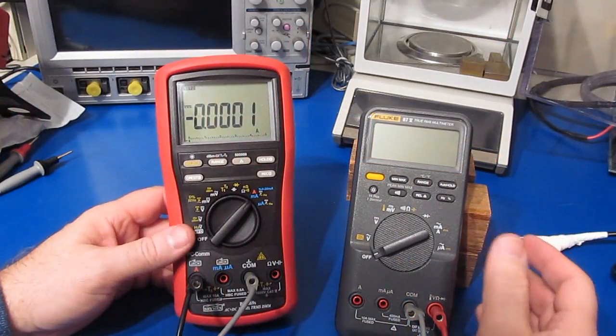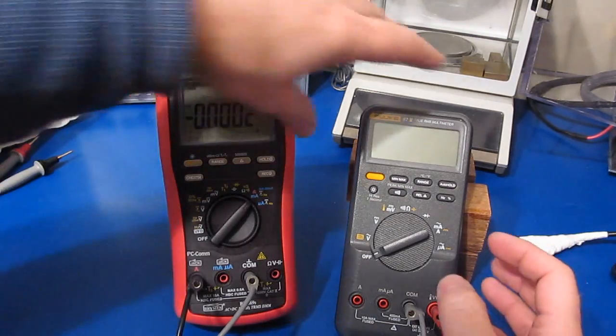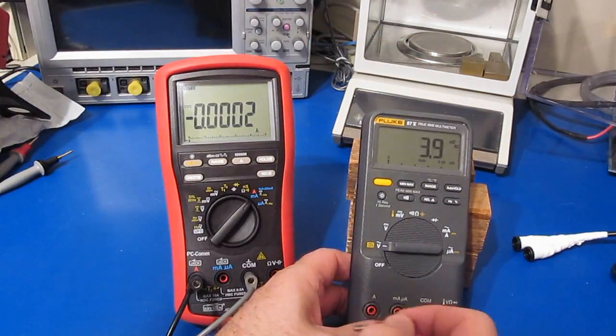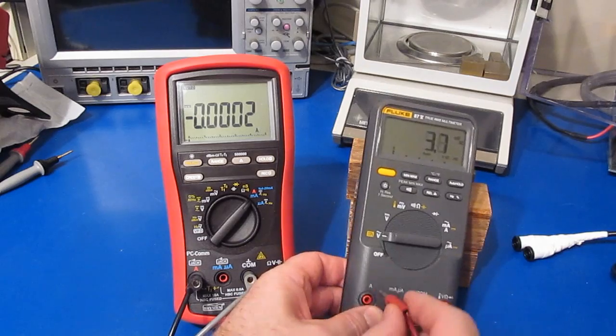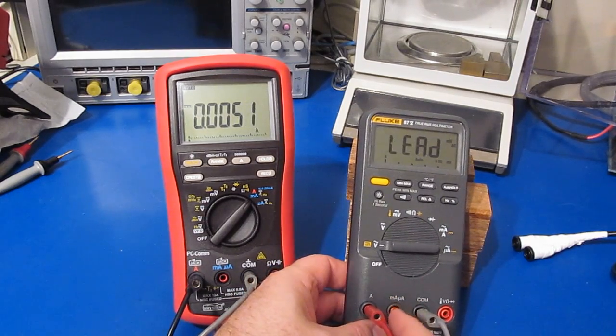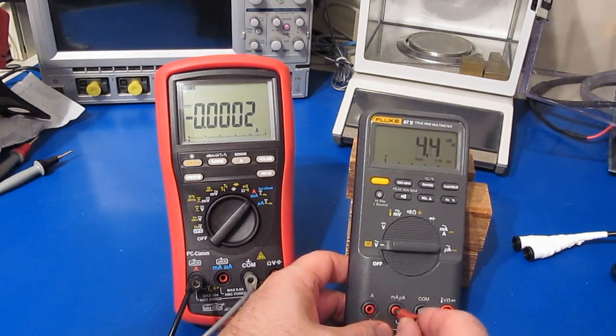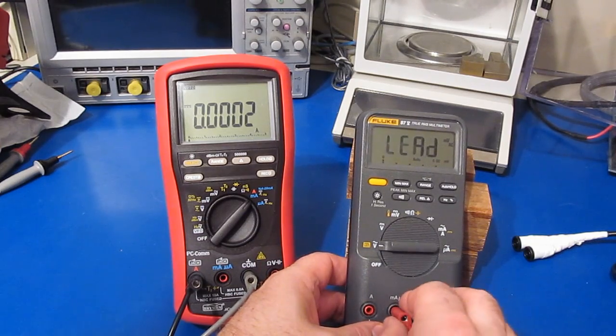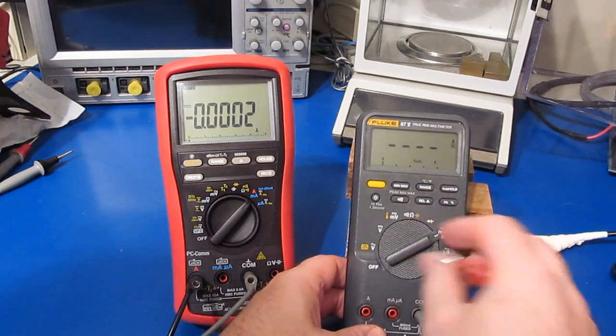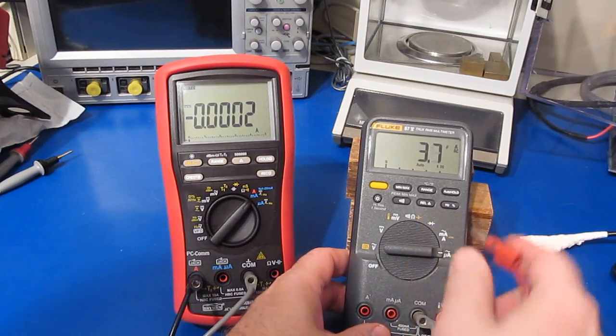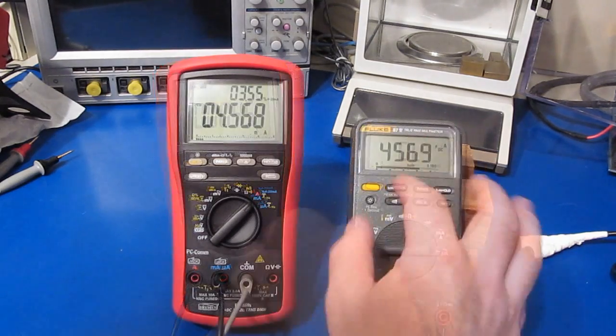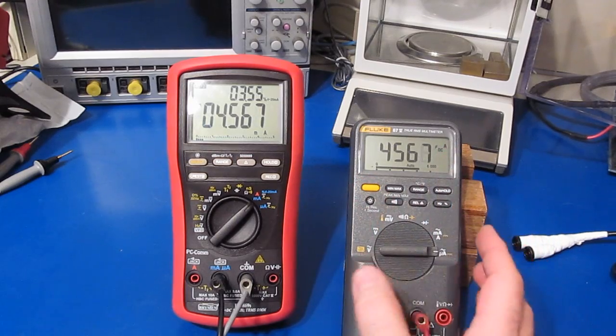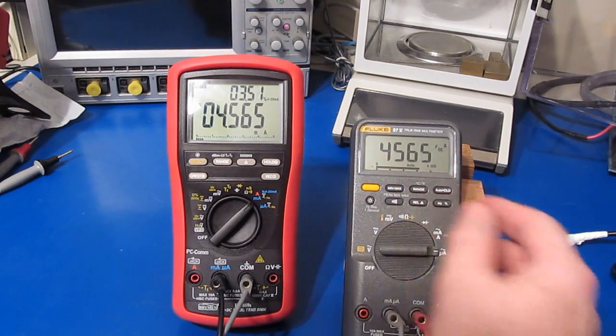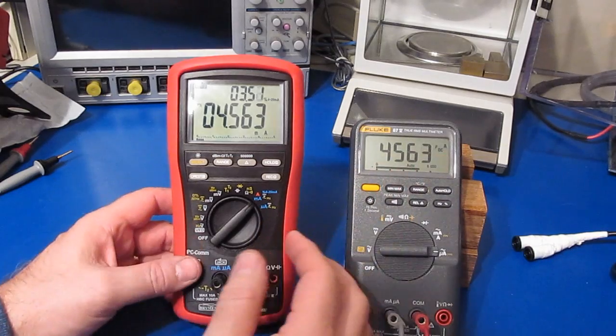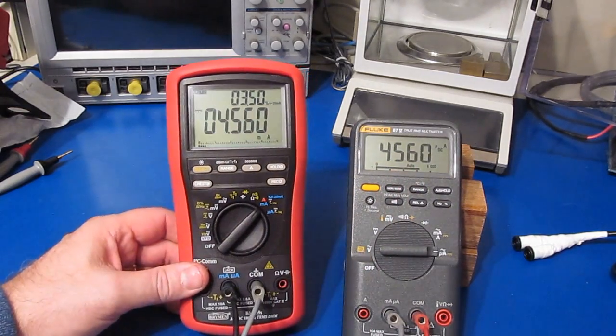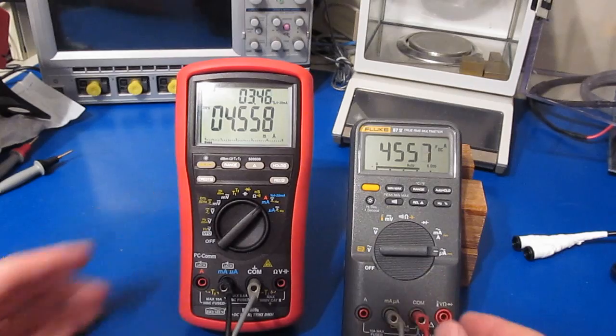Alright, I went through a full functional test except for the current input, and the meter seems just fine. So the first thing I want to do is make sure that the lead detection circuit isn't damaged. And you can see that one definitely works. Let's try this one. So no problems there. So let's just go ahead and we'll switch this over to microamps. Alright, so you can see we're in the microamp scale, and it's reading 4.565 milliamps. Very close to what the Brymen reads, so no problems there.